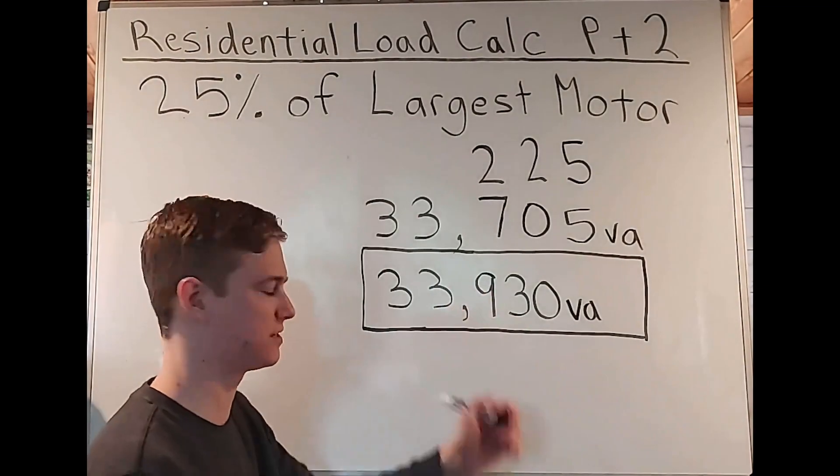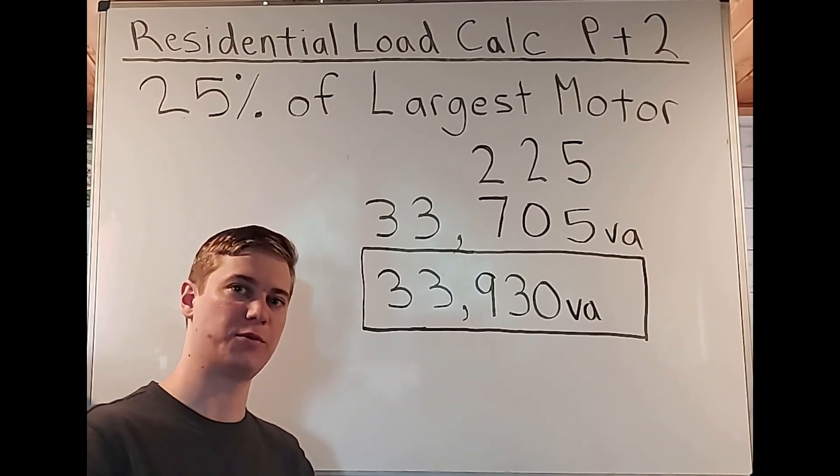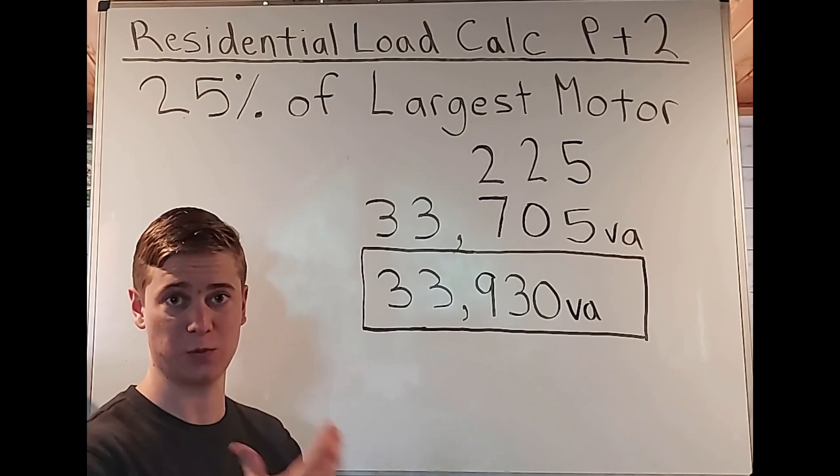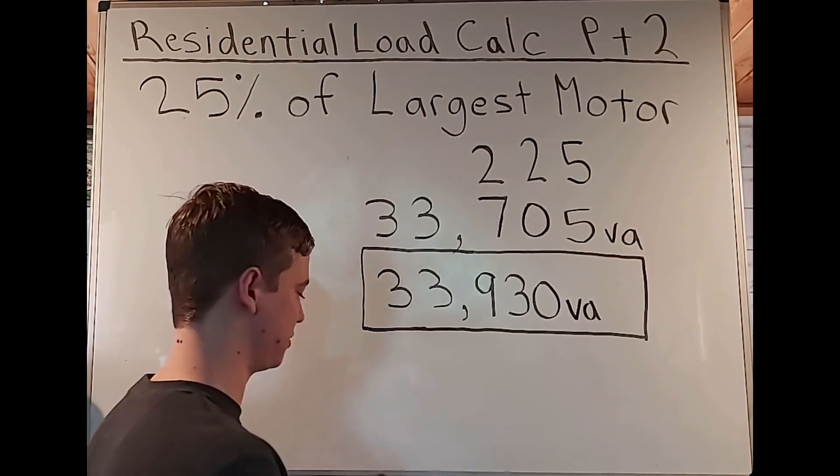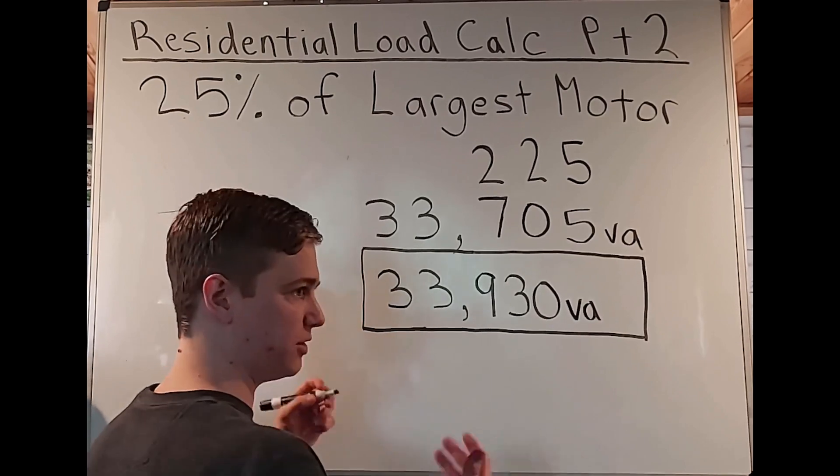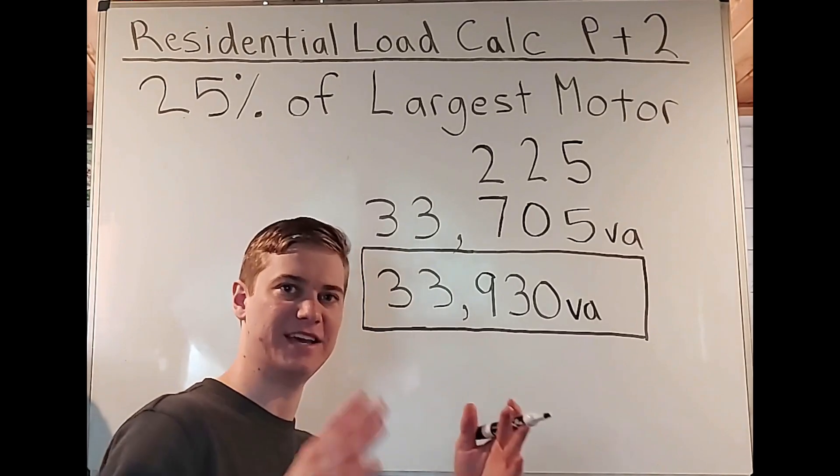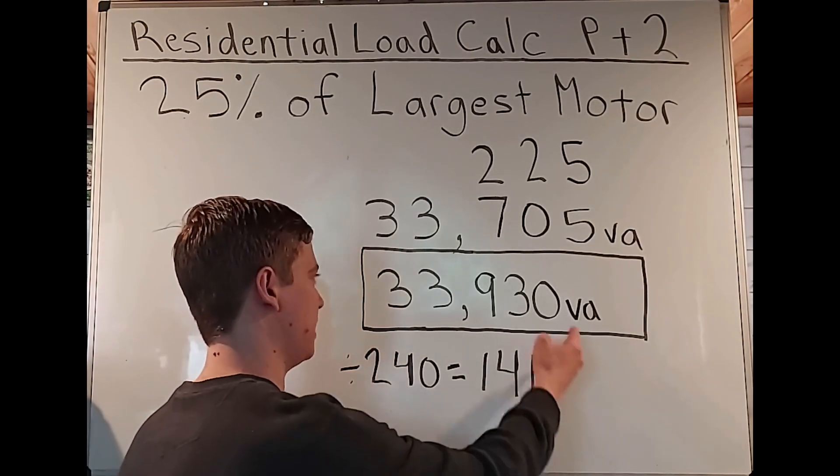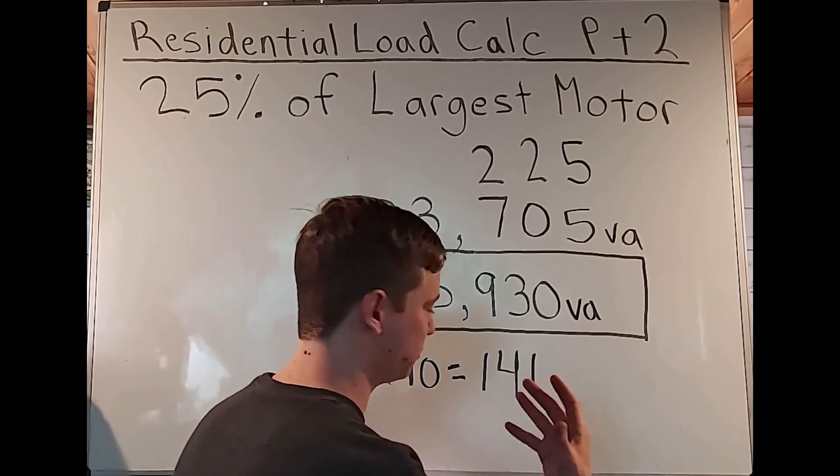Now that we know our total demanded load for that unit, what size overcurrent protection device can we use for this? And what size wires can we use with that? So to do that, we're going to get our number 33,930, and we're going to divide it by 240. Since for residential, if you look at the panel, we have an A phase and a B phase. And we come up with 141. And remember we had volt amps. We're dividing the volts. So we're left with amps.